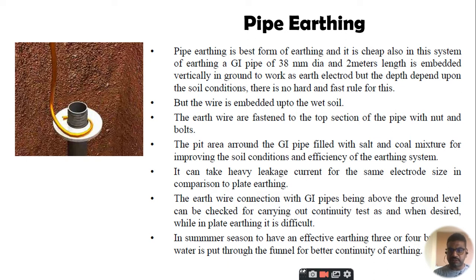For the same electrode size in the earthing, the earth wire connection with the GI pipe, being above the ground level, can be checked by carrying out the continuity test when desired, while plate earthing is comparatively difficult. In the summer season, to have effective earthing, 3 or 4 buckets of water are poured through the funnel, and better continuity of the earthing is required because the soil moisture gets very low in the summer. So this is pipe earthing.